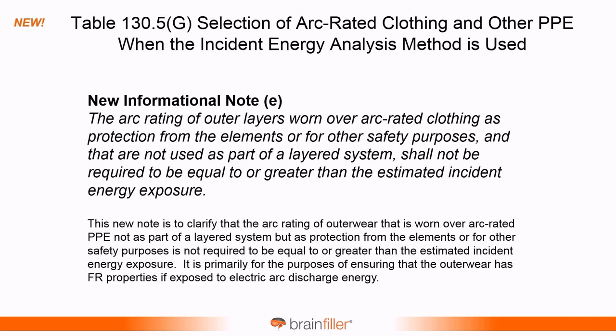Some of these changes, there was an informational note that was added. So what we have is Table 130.5(G), and this is actually for selecting PPE when the incident energy analysis method is used. There's a table for selecting PPE, and I'm going to show you kind of an excerpt of it. There were two changes made to that table. Similar changes were made to the NFPA PPE category table. So both have this similar kind of a change.